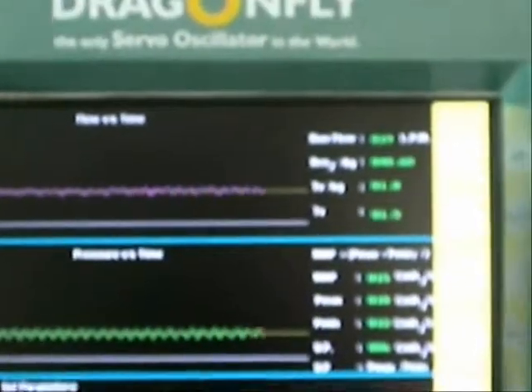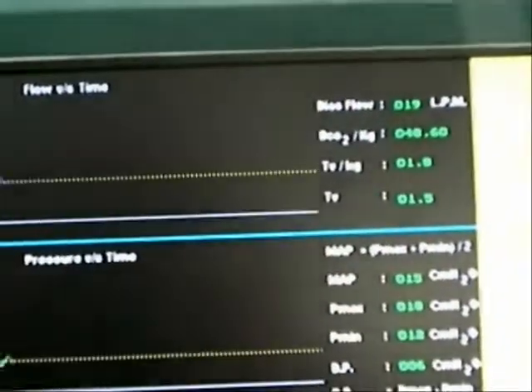Now, coming back to the screen, you can notice the tidal volume that's going to the patient. As we all know, the tidal volume delivered on high frequency is less than or equal to the anatomical dead space volume. Here you can see the tidal volume per kg is 1.8 and total tidal volume is 1.5. We have something known as the DCO2 figure. You can notice it here. Now what is DCO2? DCO2 is best described as tidal volume squared times frequency.